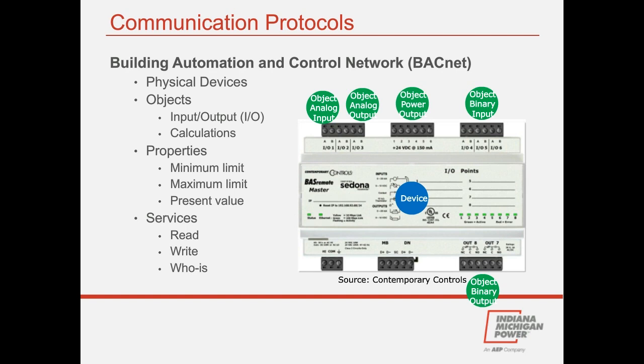Finally, we need services built into these controllers so that one BACnet device can access data from another or command another device to take action. In order to learn, for instance, what the outside temperature is, we'd use a service called read property. And we'd use a service like whois to know that you've added other devices on the system.